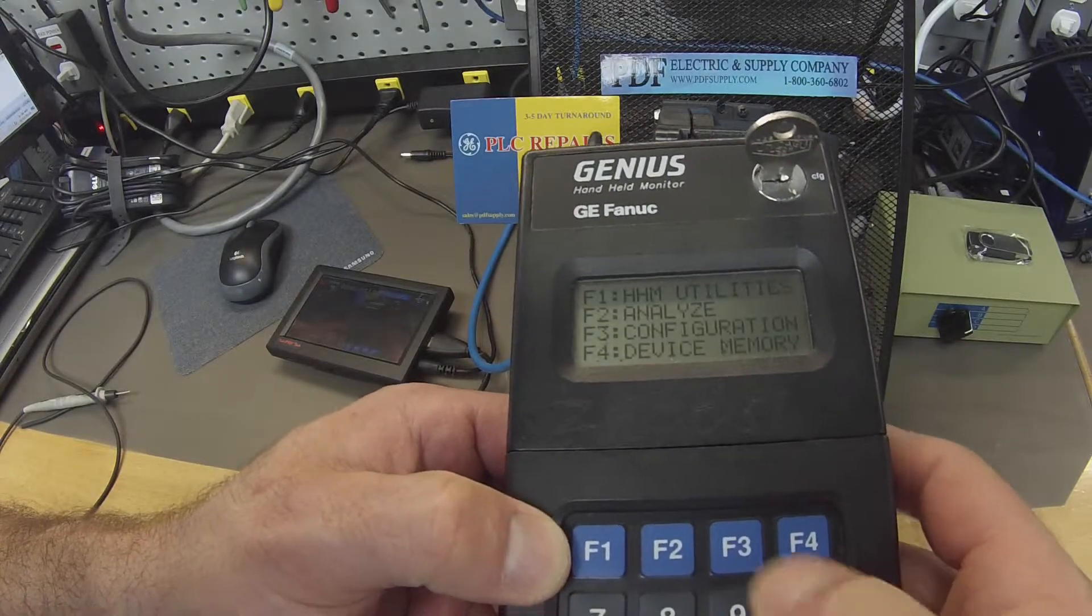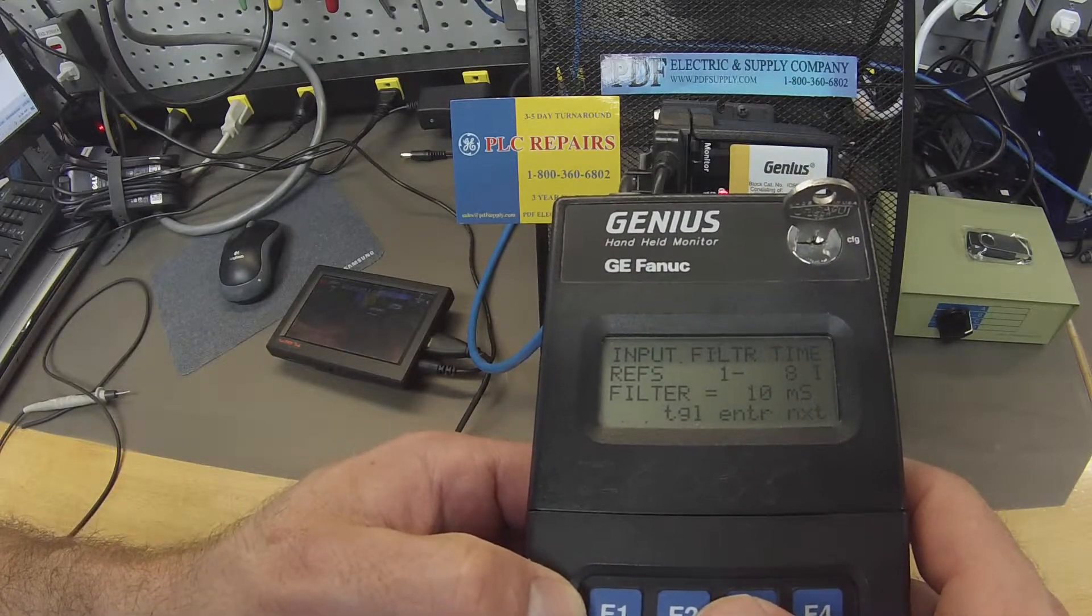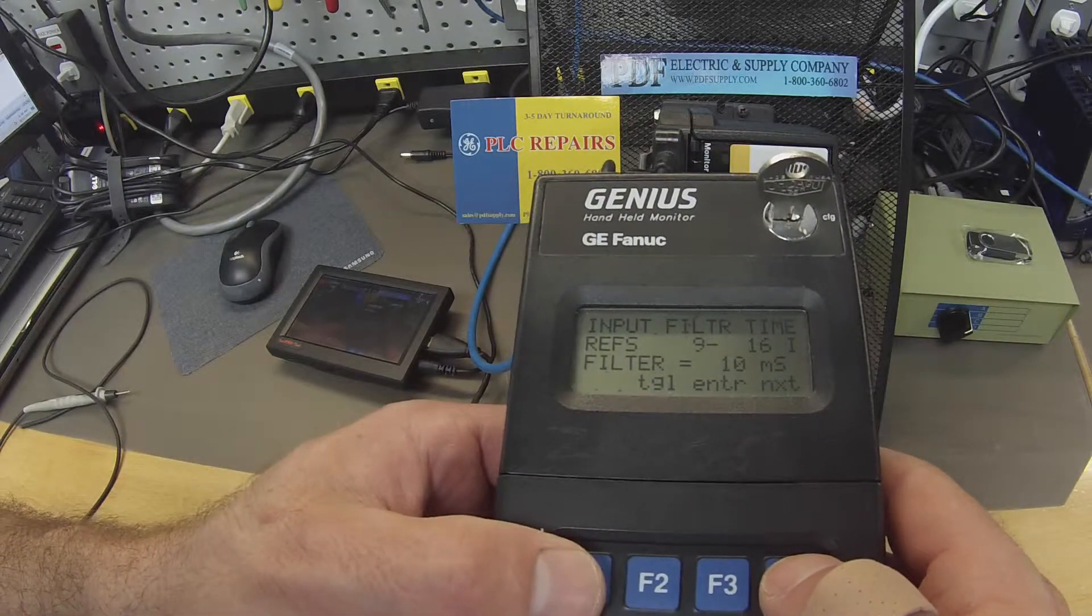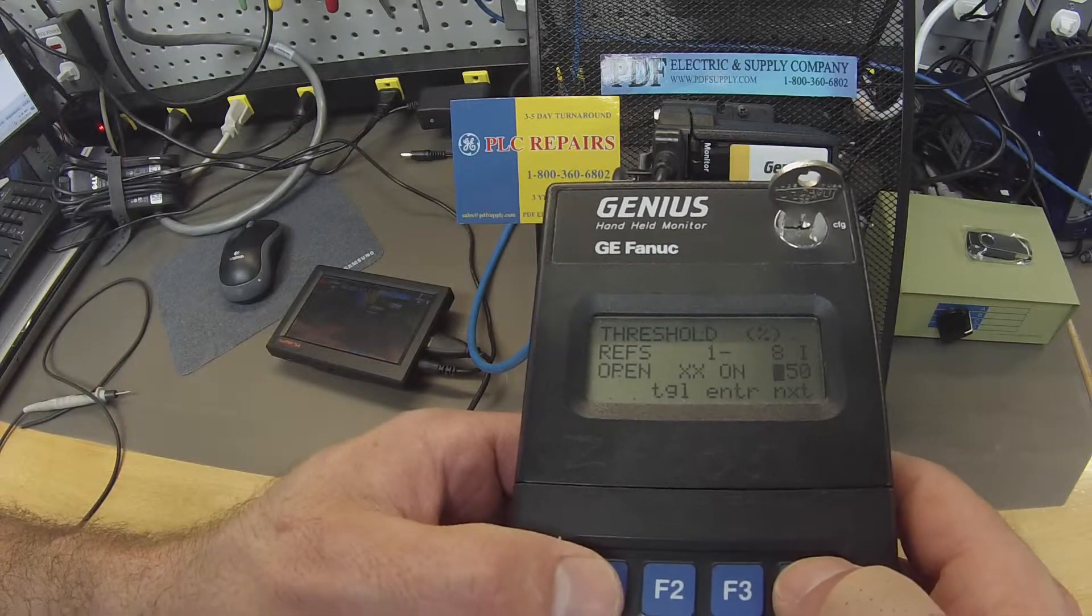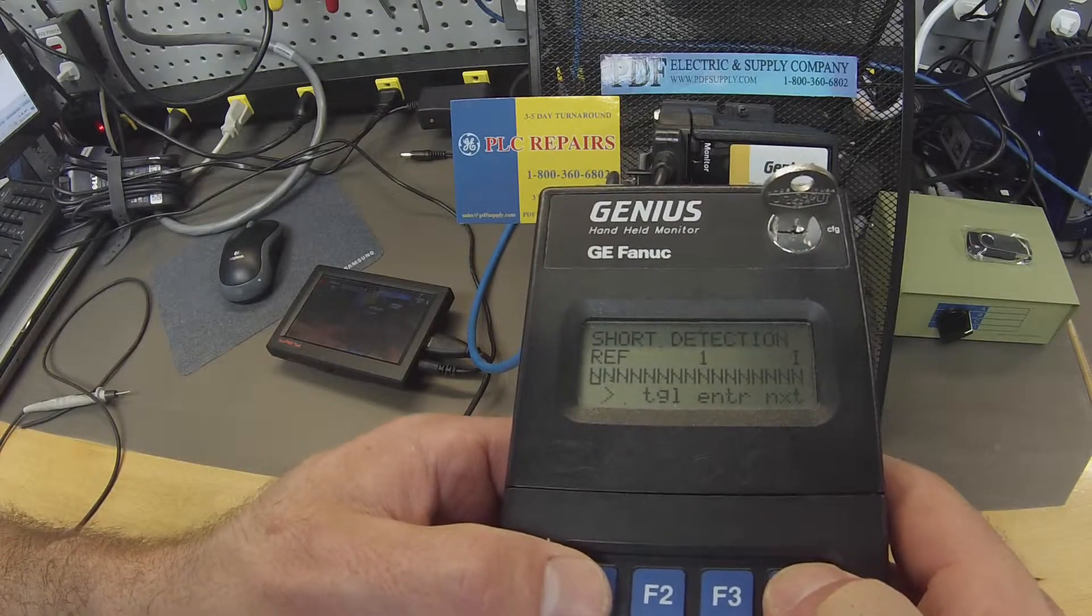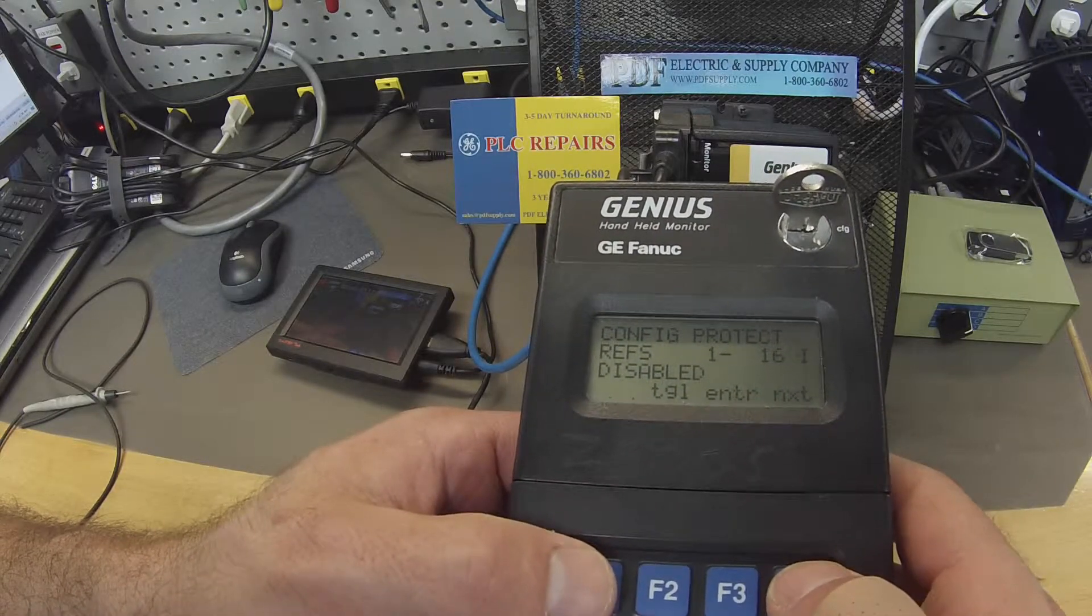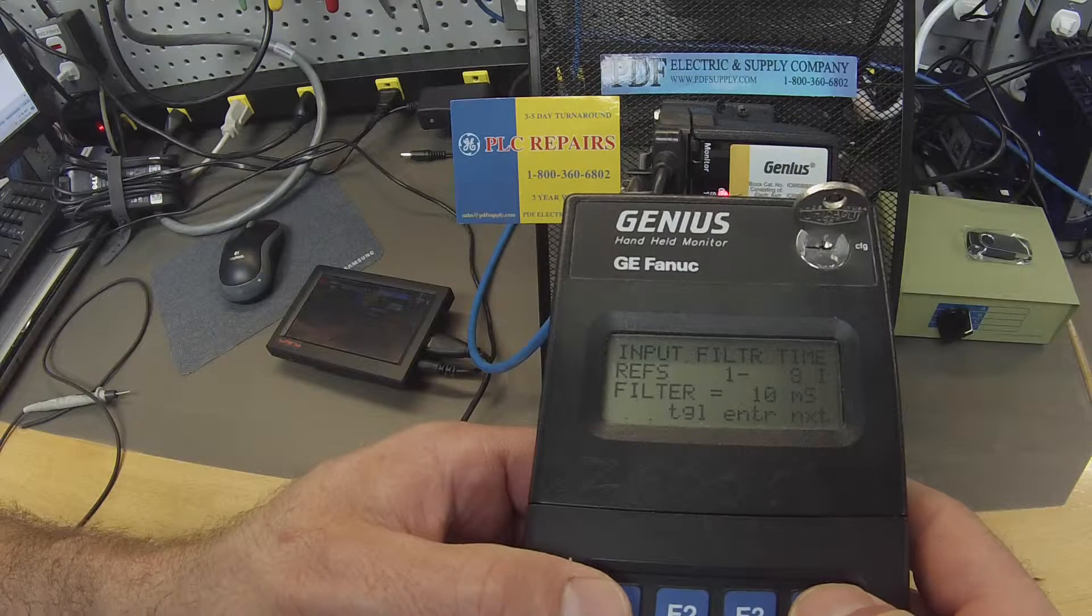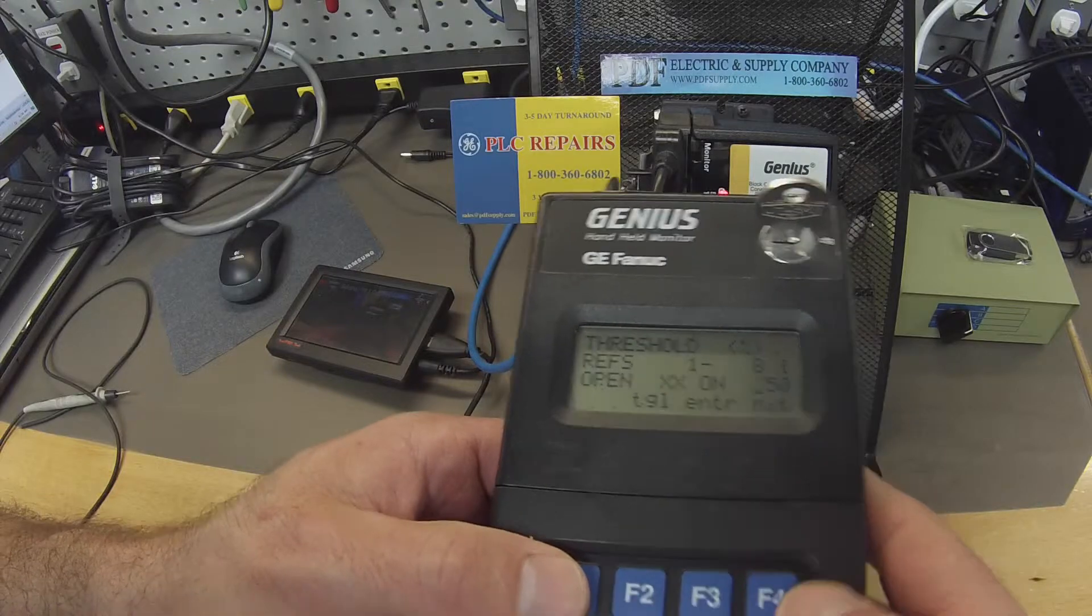I'm going to go back to home, configuration, configure block. Now the rest of this is the factory settings, 10 milliseconds. Next, 9 through 16, 10 milliseconds also. Threshold at 50, 9 through 16. Report faults, yes. Short detection, no. Open wire detection, no. Configuration protect, I have it disabled so that I'm able to make changes but you guys can enable it once it's set the way that you want it. Input filter time, 10 milliseconds and that's for all channels.